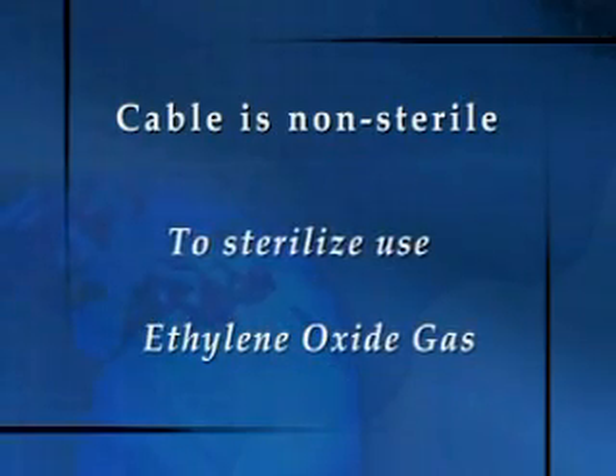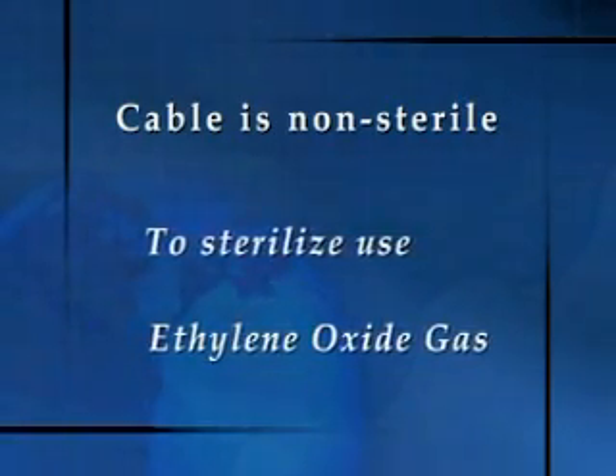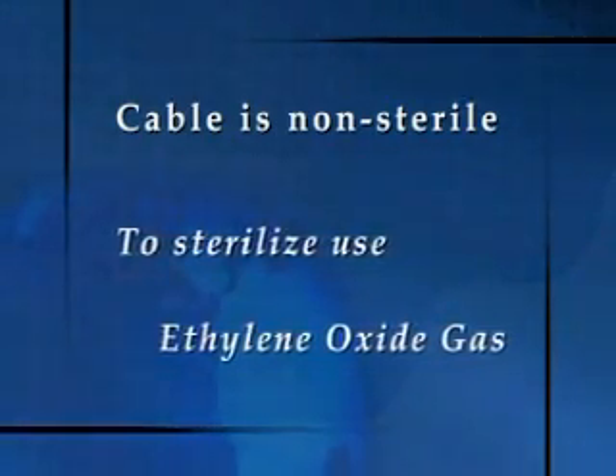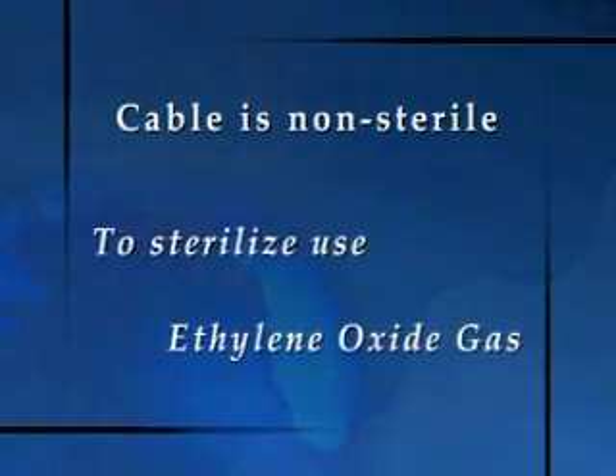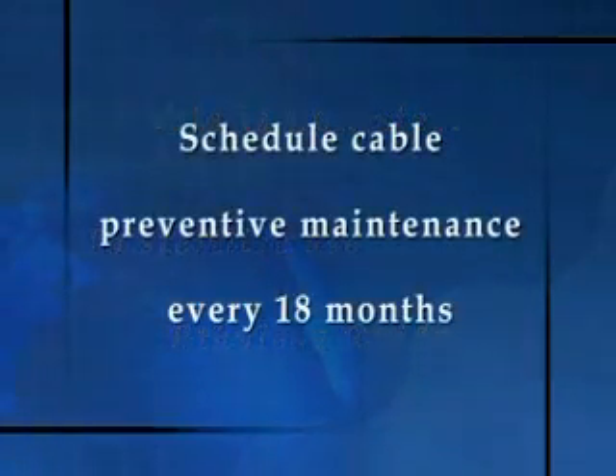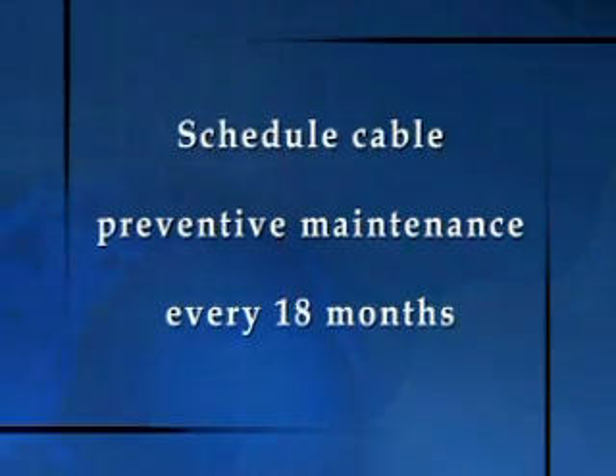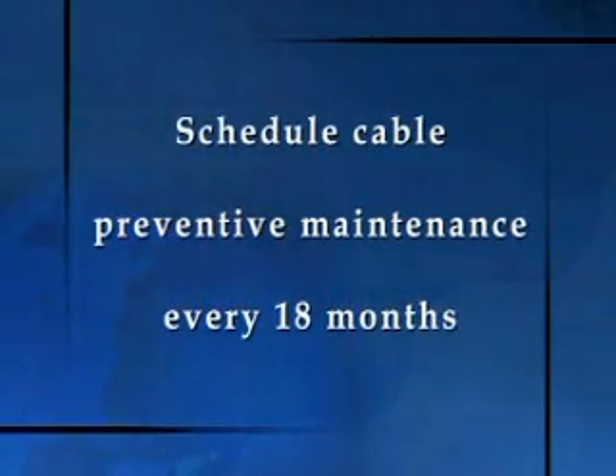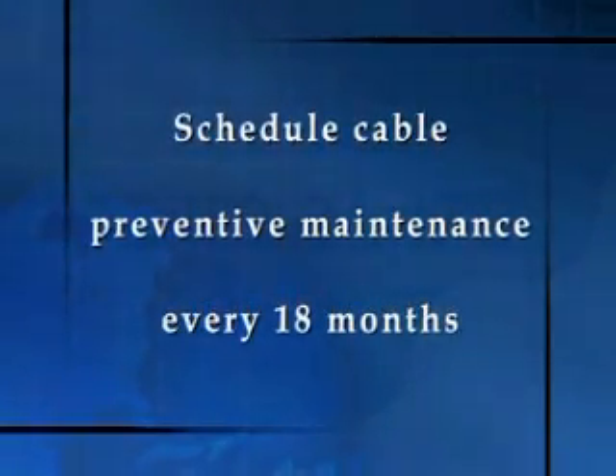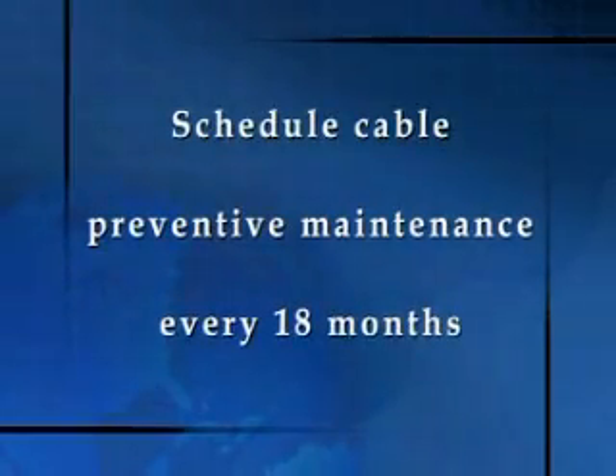If necessary, the cable may be sterilized using ethylene oxide gas only. To maintain optimal cable function, it should be returned with the monitor when sent to Integra Neurosciences for preventive maintenance. This maintenance is recommended every 18 months for the MPM-1. The cable will be checked for wear and replaced if necessary.